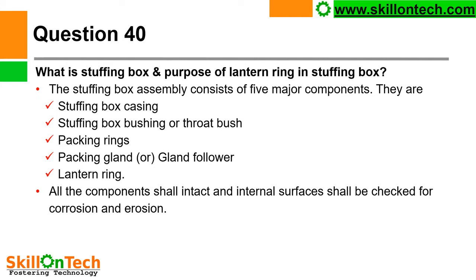What is the stuffing box and the purpose of the lantern ring in the stuffing box? The stuffing box assembly consists of five major components: stuffing box casing, stuffing box bushing or throat bush, packing rings, packing gland or gland follower, and lantern ring. All components shall be intact and internal surfaces shall be checked for corrosion and erosion. We shall see the picture of the stuffing box in the next slide.